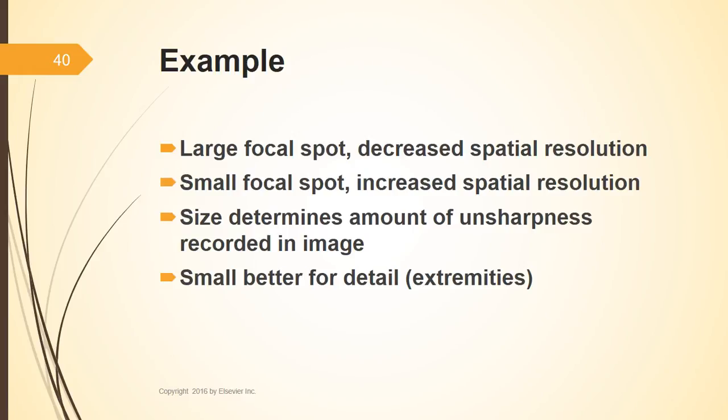If you're radiographing a larger area, then you want a large focal spot size. And that's usually like for an abdomen, even a chest x-ray. So when you think of your body, look at your hand and then look at your abdomen. Even if you're a skinny person or a small person, your hand is so much smaller than the abdominal area. So if you are radiographing something larger, pick the larger focal spot.